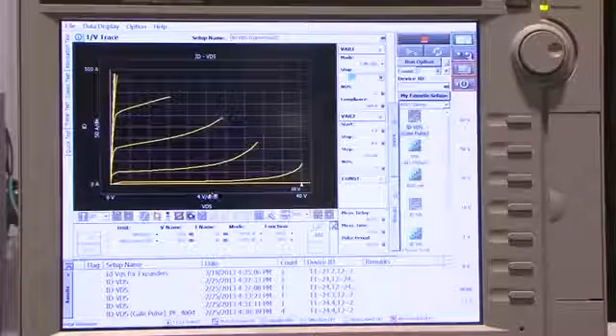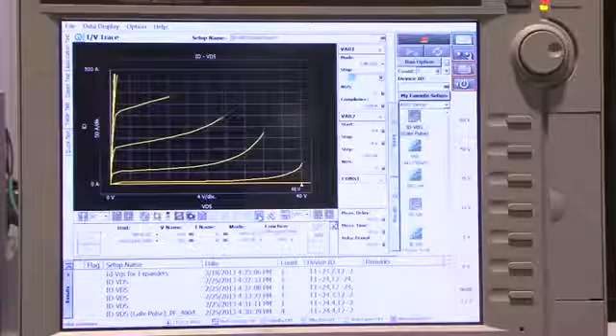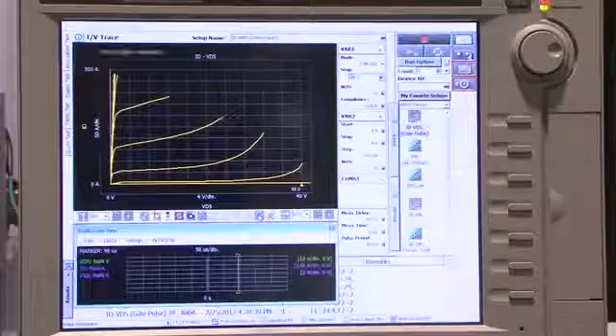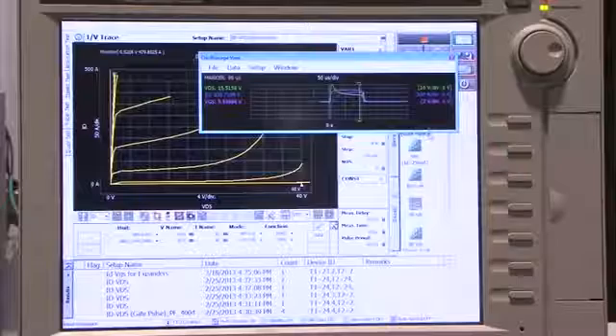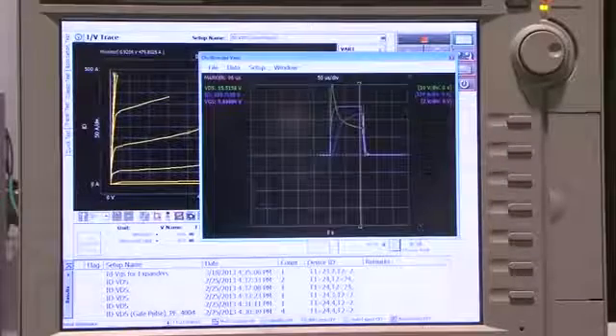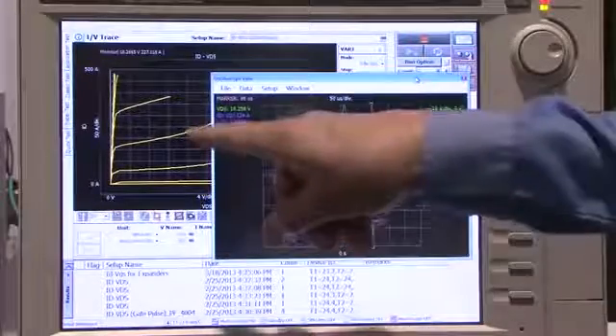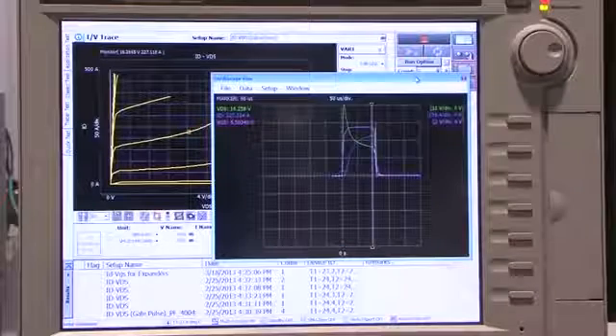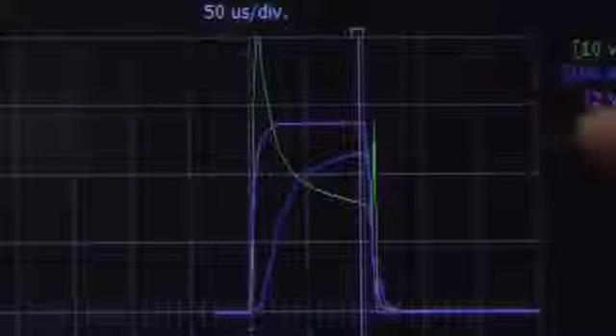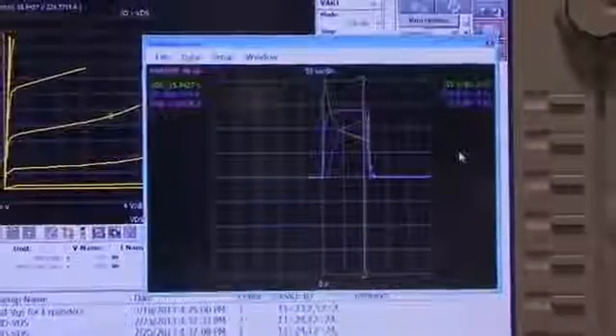And the other neat feature is that on this product, I can actually go in and look at any point on this curve and see the pulsed waveforms. So of course, because it's a power device, everything has to be pulsed. So notice the little mark over here that I'm looking at the waveforms on that point. So here you can see that I can see the drain voltage, drain current, and gate pulse all here on the screen. And I can verify with this little timing window that I've actually got stable waveforms. So this is a very important feature for power devices because you need to make sure that your waveforms are stable when you're making a measurement. And this eliminates the need to use a separate oscilloscope for this measurement.